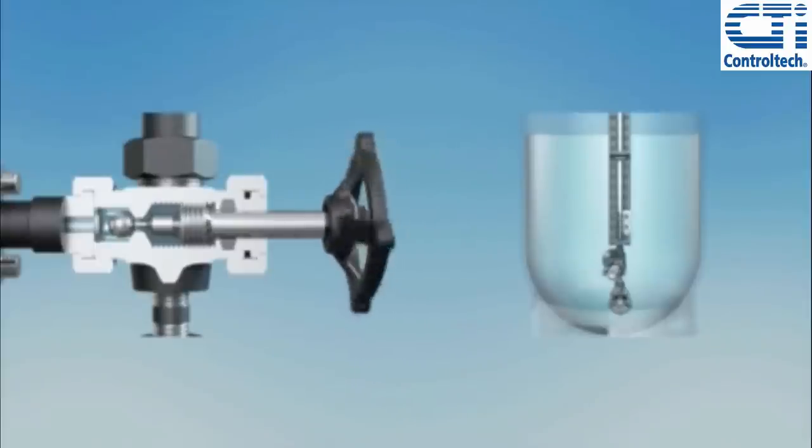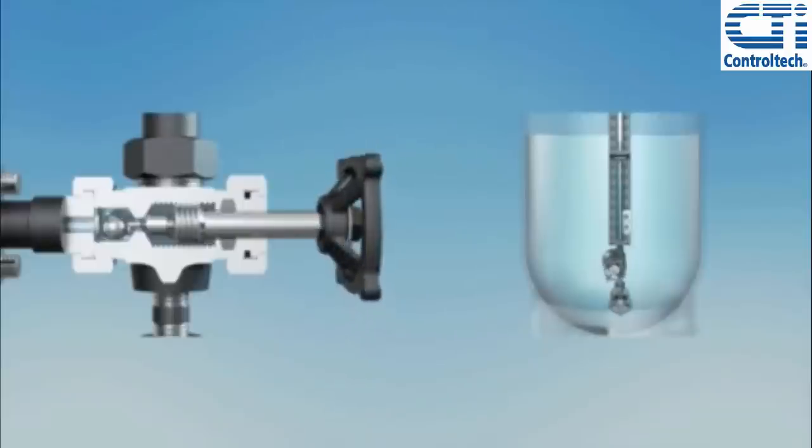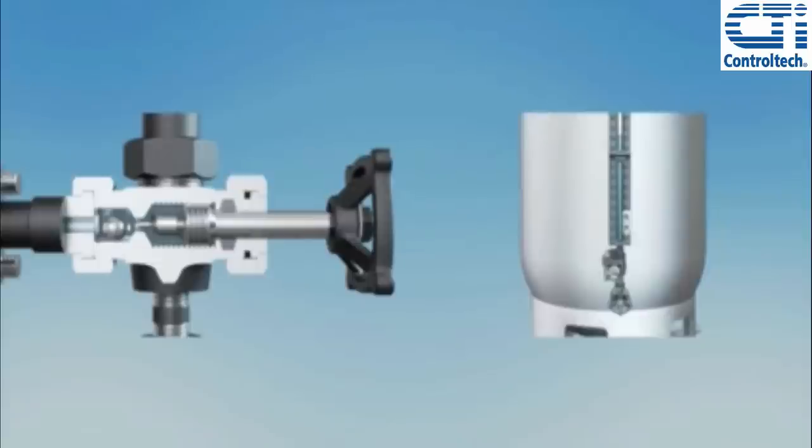the liquid's kinetic energy will force the ball check onto its seat, adversely isolating the gauge from the vessel. The gauge will then display a constant false level reading until the ball check valve is reset or the vessel level coincidentally drops to the frozen gauge level.